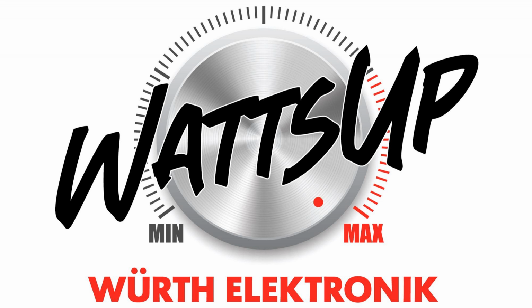So I can see that I have a good reduction at high frequencies of common mode, but at lower frequencies, so-so. Yes, I have an important reduction, but you always have to take care that this is a measurement that is done not in a shielded environment. So maybe I can have something that is coupling or whatever. So I'm not so far from the limit, and measurements of common mode especially are highly affected by the setup, by ground connection. So I will have to do something more.